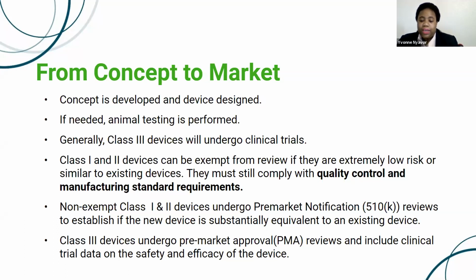will undergo 510(k) reviews. 510(k) is a pre-market notification review process. And this process is basically to establish if the new device is substantially equivalent to an existing device. So if an existing device is available for comparison, and that device has already gone through testing and all of that, it makes it easier to take this new device and compare it to the existing one and then establish similarity or equivalence, basically. Class 3 devices undergo pre-market approval, which is a pretty more intense process, of course, given the significant risk associated with them. And typically will include clinical trial data on the safety and efficacy of the device.